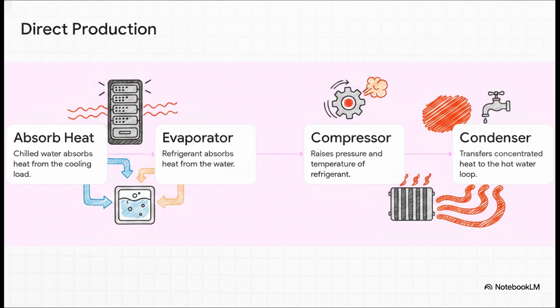Let's walk step by step through this refrigeration cycle to see how it basically acts like a direct water-to-water heat pump. Step 1. Chilled water absorbs heat from a cooling load, say a really overheated data room. Step 2. Inside the evaporator, the refrigerant absorbs that heat from the water. Step 3. The compressor kicks in, significantly raising the pressure and temperature of the refrigerant. And finally, Step 4. The condenser transfers that highly concentrated heat directly into a hot water loop used for perimeter heating or domestic water. It pulls heat from one part of the building and instantly delivers it to another.